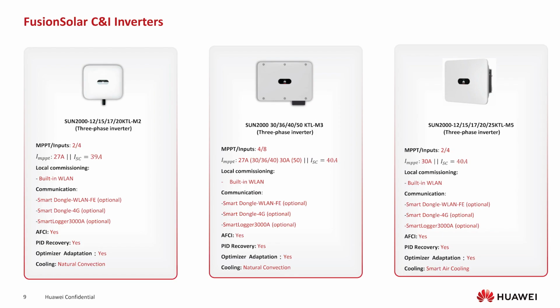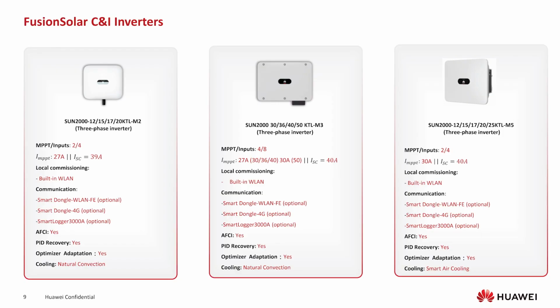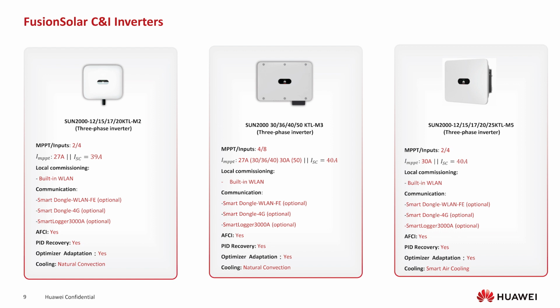So we have the smaller range, for your smaller sizes: 12 kilowatt, 15, 17, and 20 kilowatt. This has 2 MPPTs, 4 inputs, so 2 inputs per MPPT. The MPPT current is 27 amps, and the short circuit current is 39 amps. This comes with built-in WLAN, but you can also add communication devices like a smart dongle, smart dongle 4G, or the smart logger. This comes standard with arc fault circuit interrupter, which I will talk about later. It also comes standard with PID recovery, and it has the ability to use optimizers. This has natural convection cooling, so there are no fans in the smaller ones.